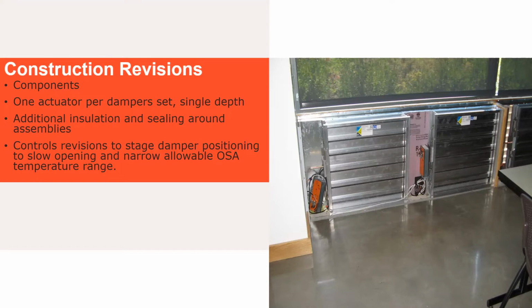High quality components and sealing get rid of 95% of your issues there. And accessibility - you need to be able to monitor somehow that you're not having leakage. If you had an inlet temperature sensor for a couple of these, you could say, oh, I'm seeing 55 degrees inside the space. You'd want to mount it a few inches away, well insulated, maybe an insulated damper set, so you can see a baseline and have some alarming capabilities.